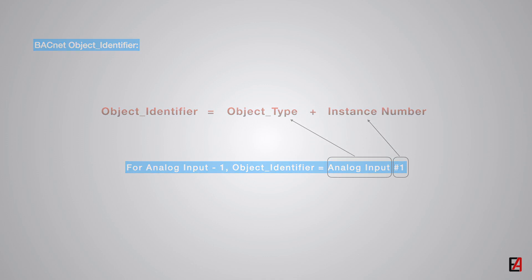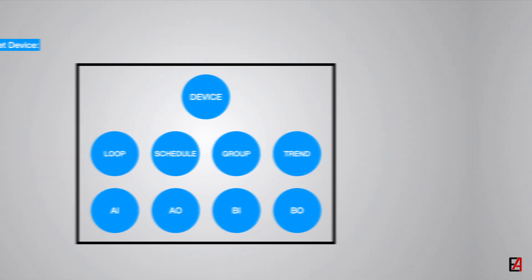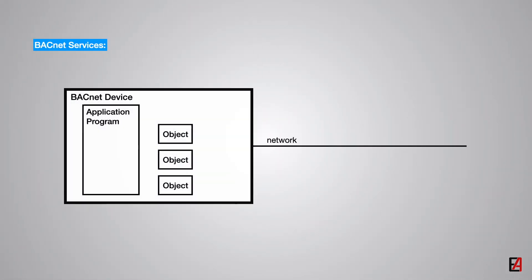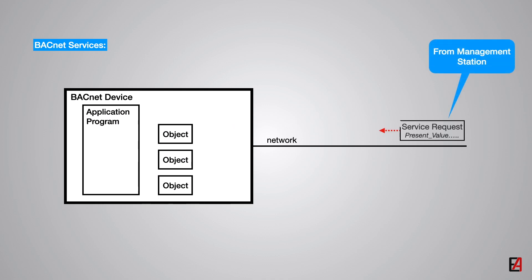A BACnet device is a set of BACnet objects. Next in the BACnet specification is the BACnet services. One BACnet device obtains information from another device or commands another device to do some actions by means of services. Each service request issued and service reply returned becomes a message packet that is transferred over the network from the sending to the receiving device.